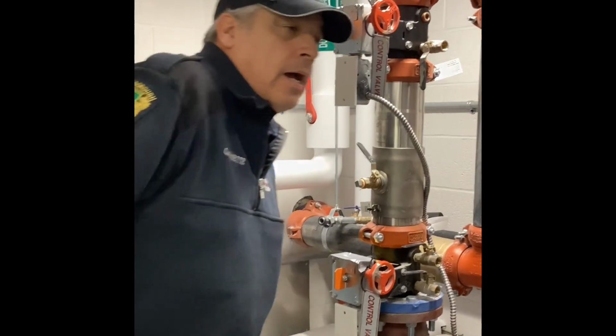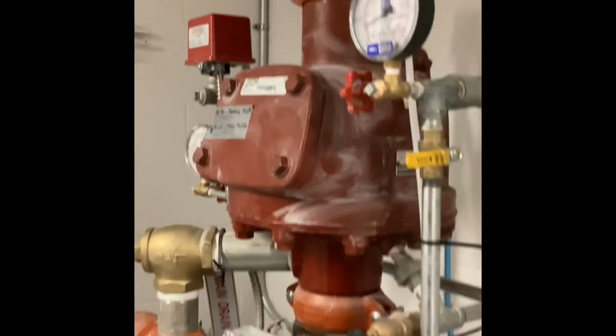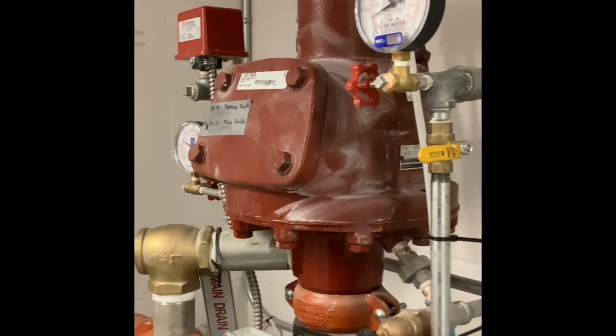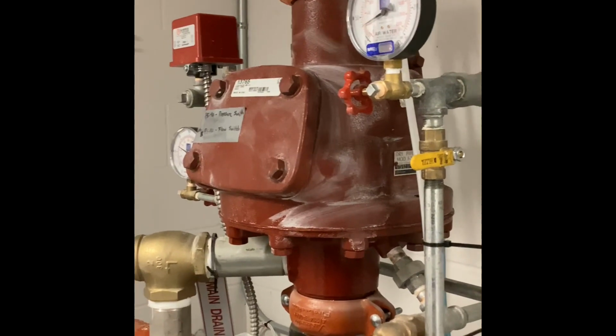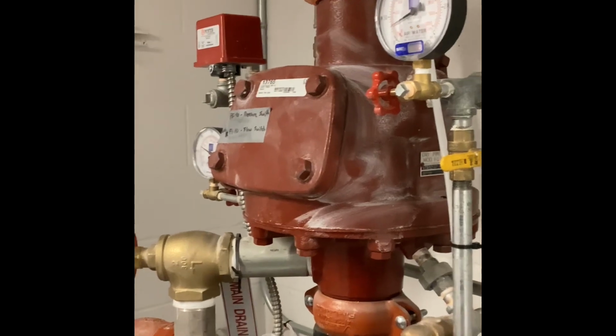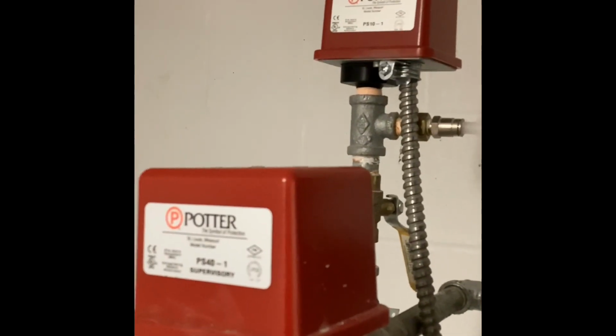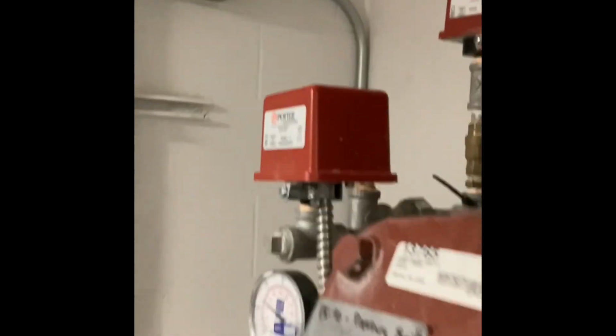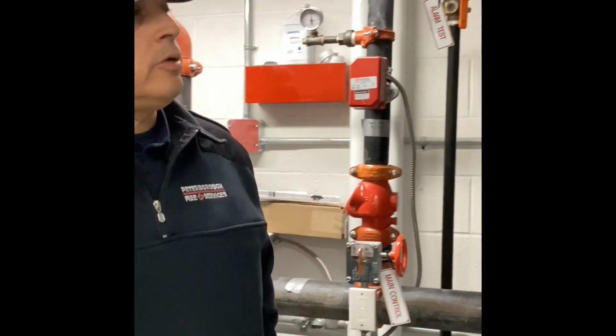It ends up bumping a bladder that's back off on that pipe right there, so the pressures equalize. That sends the system into alarm, basically saying we have some flow going on. The system itself has no idea what's happening, it just knows something's changed and the pressure's equalized. It figures water is falling somewhere from one of the discharges, as per design. Again, it's a piece of machinery, it can be tricked.